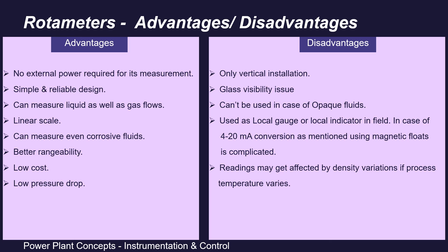Talking about advantages: first, it needs no external power for its working, unlike other flow meters. Second, it has a very simple and reliable design. It can measure liquids as well as gas flows. Its scale is approximately linear. It can measure even corrosive fluids. It also has better rangeability, low cost, and low pressure drop.